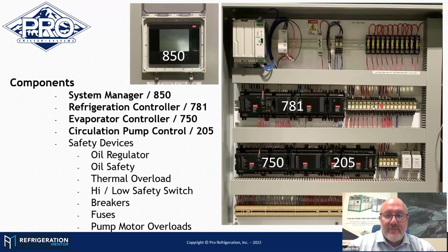You know, there's a bank of ice cube relays over here on the side. Sometimes, the majority of the time, there's nothing wrong with the controller. You've got an ice cube relay that's not getting the right voltage. Or I'm just going to share some examples. I've had communications alarms that were intermittent and pop up from time to time. Well, on the 781, if you notice right here in the front, this is the communication bus where it makes the connection. So it makes this connection from the 750 is here, and then this follows the raceway up to the 781, and then that's fed over to the 850.